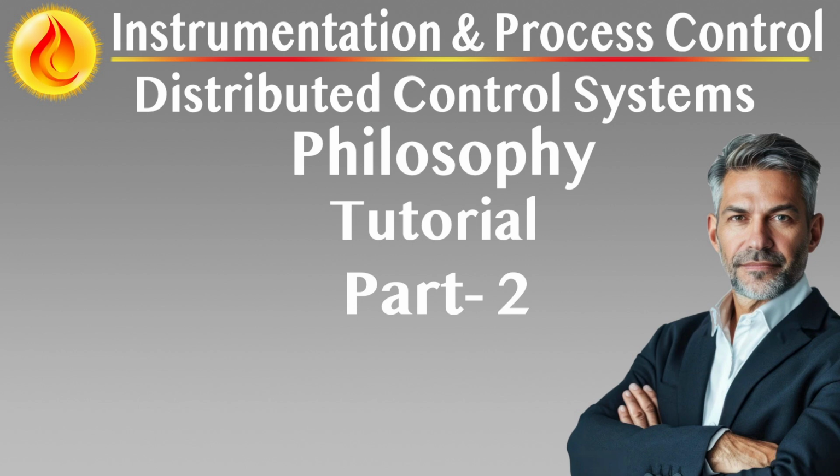High-speed deterministic execution. Execution time from input detection to output actuation is optimized with scan cycles under 20 milliseconds. Safety-critical paths use deterministic communication buses, e.g., Profinet safety, EtherCAT safety, and pre-configured cause and effect matrices validated during commissioning.